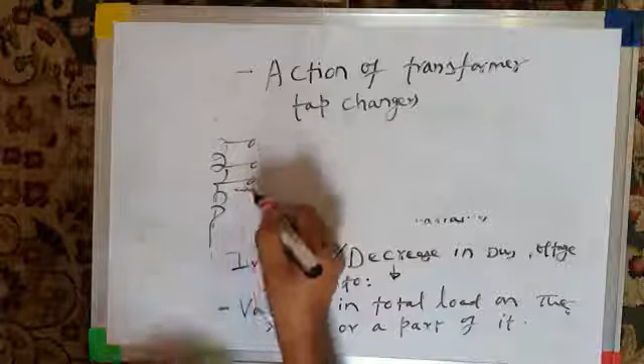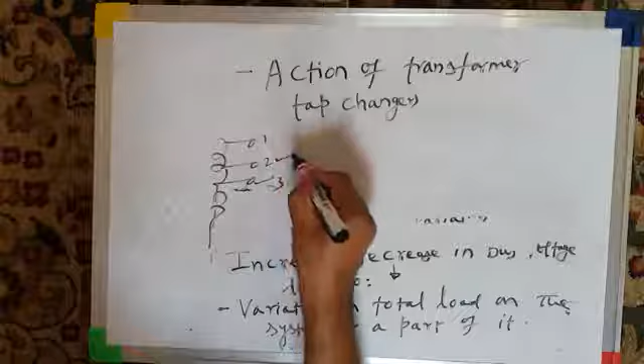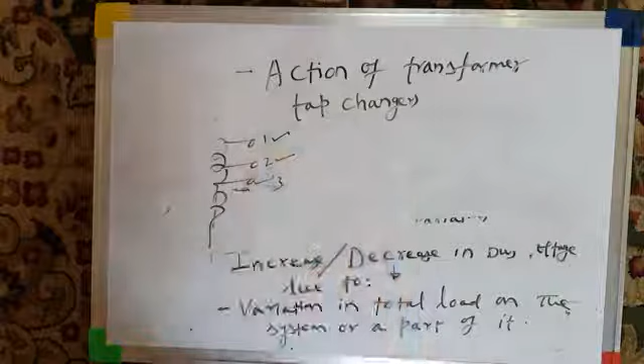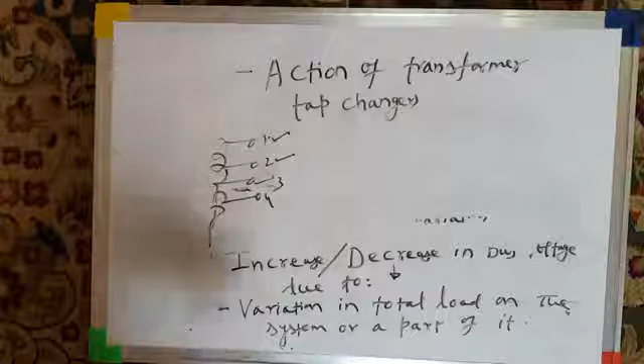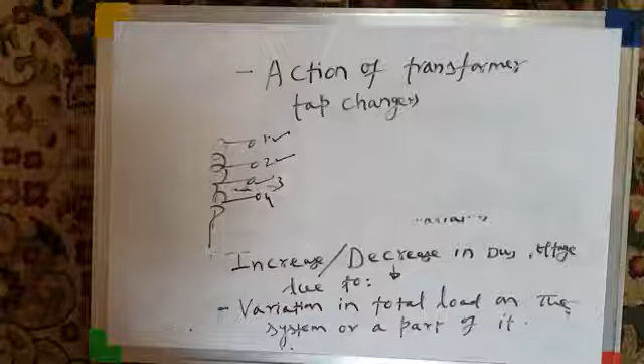If you are operating the transformer on a lower tap, the voltage is low. So suppose you go to tap 1, tap 2, tap 3. If you go from tap 3 to tap 2, what will happen? Voltage will increase. If you go from tap 2 to tap 1, voltage will further increase. If you go directly from tap 1 to tap 4, voltage will decrease. So if transformer tap changing takes place, that also is responsible for increase or decrease in the bus voltage, and hence voltage magnitude variation.